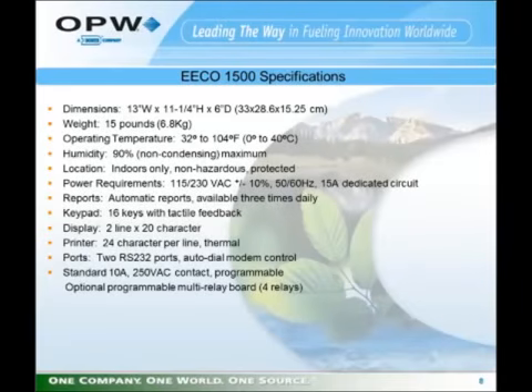The EECO 1500 specifications. On this slide you can see the dimensions, the weight, the operating temperature, humidity. The important fact on this list is this device is designed to be installed in an environmentally controlled atmosphere. Above freezing, below 104 degrees Fahrenheit, less than 90% humidity. Indoors only, non-hazardous. It will operate on either 115 volts AC or 230 volts AC, but we require a 15 amp dedicated circuit for power.